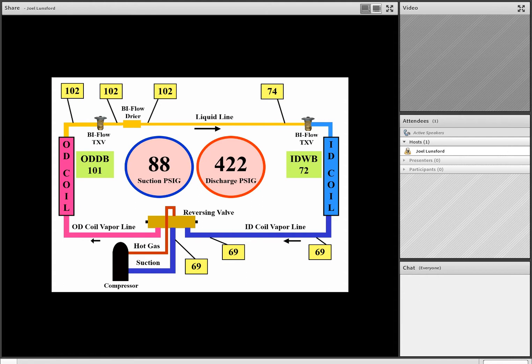It could be a kink, it could be an undersized line, it could be a fitting that's been filled up with solder or braze material. So in this example, we have a restricted liquid line that we'd have to address, find out why, and correct. So a restricted liquid line. And the big thing that we found, team, was a low suction pressure, high superheat on the cold coil, and a big temperature drop across that liquid line.